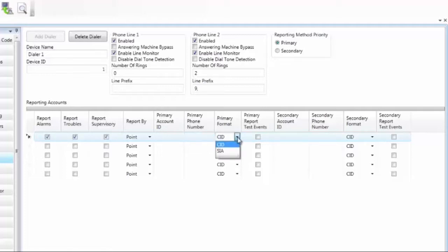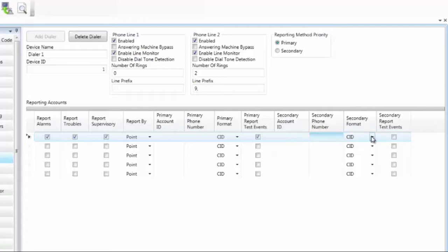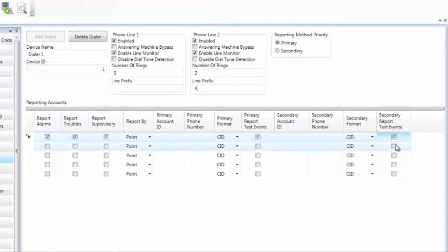We have two formats, contact ID or SIA. The default is contact ID. And test events. Do you want test events to be sent to central station? Go ahead and check this box. They will probably also give you a backup phone number to go to a different receiver. That would go under your secondary phone number. They may potentially give you a second account number. Chances are this is going to be the same as your primary. Again, if this is a different receiver that you're going to, they may actually have you have a different format. Again, it's contact ID or SIA. And again, test events to that secondary receiver or not.